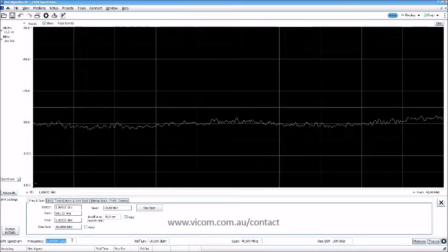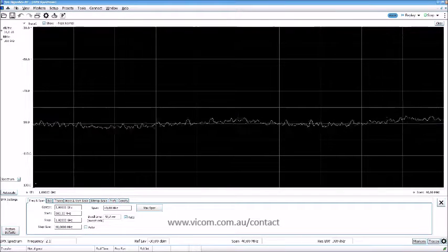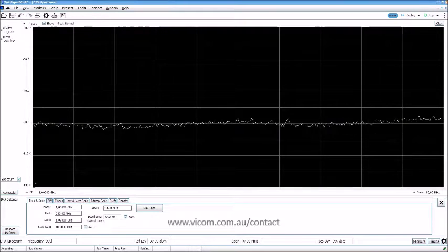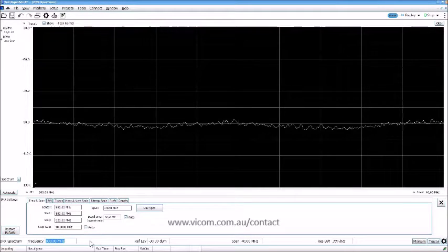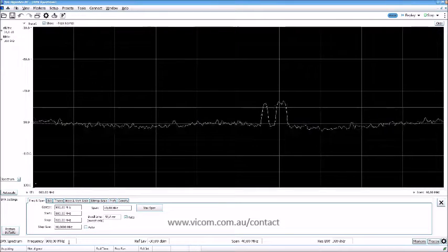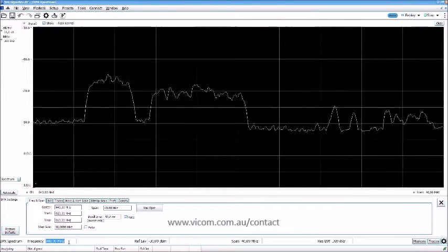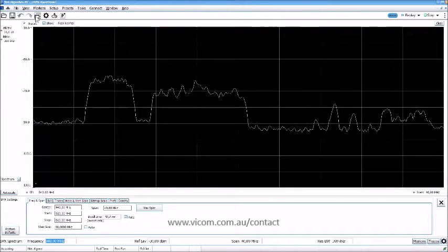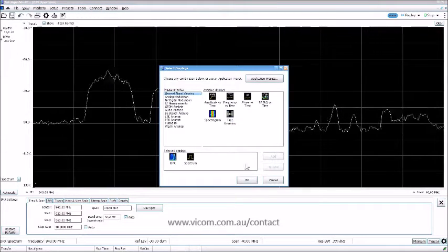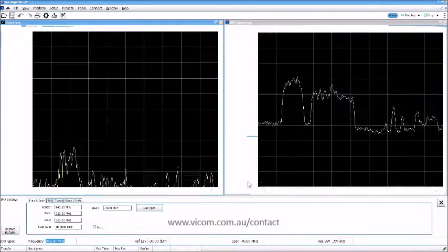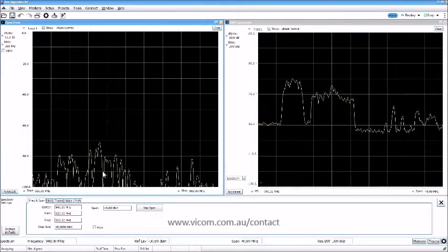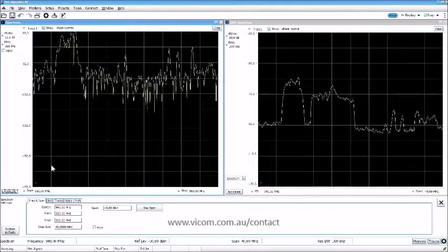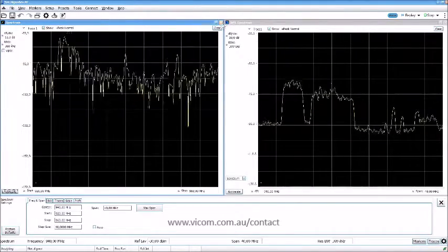I change the step size to 40 MHz to make it a little faster, then sweep around 1 GHz or 900 MHz — it doesn't really matter. Now when I go up I move four steps at a time, and here we have some signals on screen which look really nice compared to the normal spectrum view.